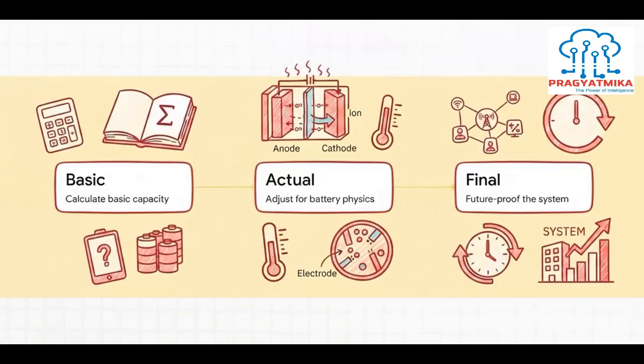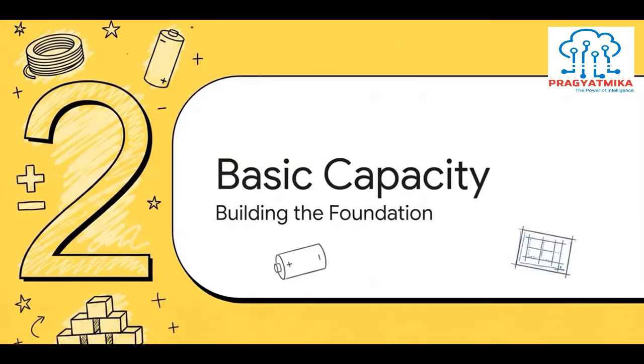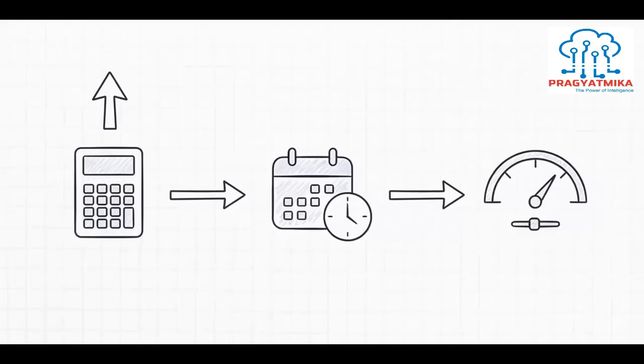So now that we know we're sizing our batteries for that marathon, let's look at the actual 3 steps: basic capacity, actual capacity, and final capacity. This is the definitive calculation process the pros use. Step 1, basic capacity. Building our foundation. This is where we get our raw, completely unadjusted starting number. To find it, we take the total daily load in kilowatt hours and multiply it by our desired backup days, also known as your autonomy.